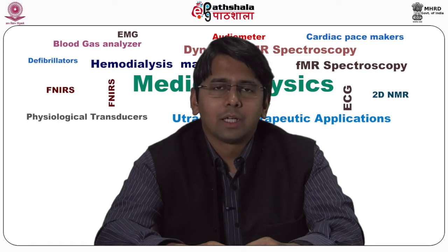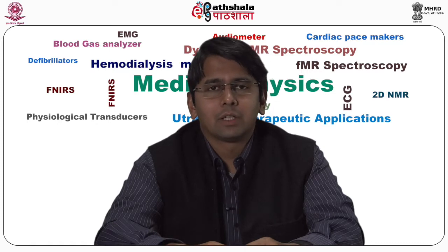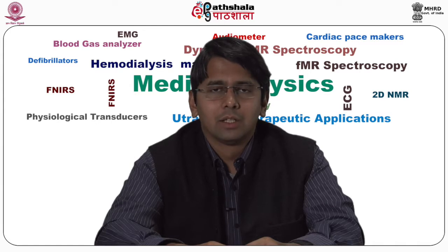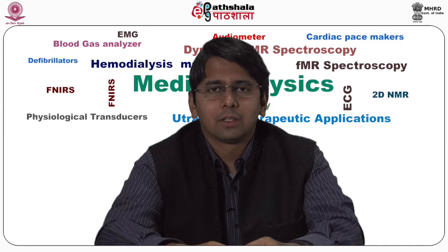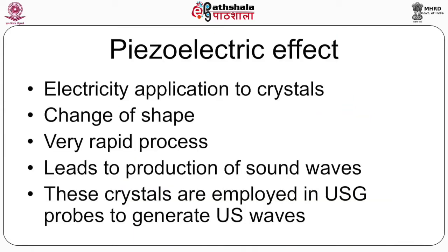As I talked about earlier, this effect was discovered in quartz crystals, which have regularly spaced molecules arranged in a lattice or in a definite geometry. Whenever electricity was applied to this crystal, it went into a different shape. This change of shape was a very rapid process. Now, this brief change of shape led to production of sound waves. These quartz crystals are at the heart of ultrasound and are used in ultrasound probes to generate ultrasound waves.